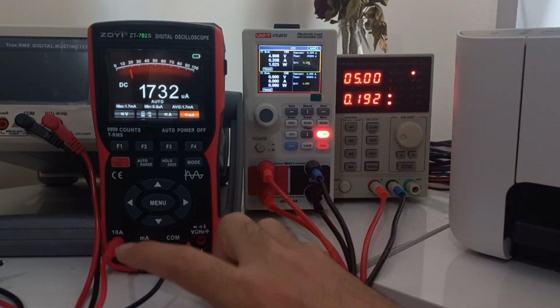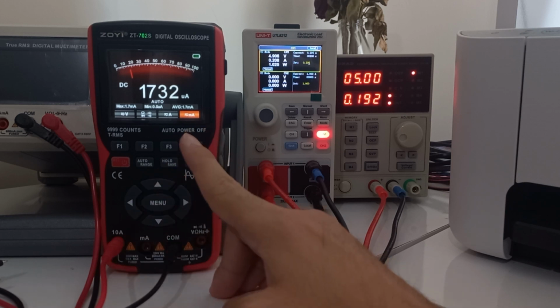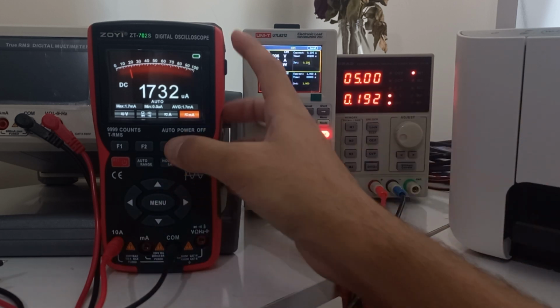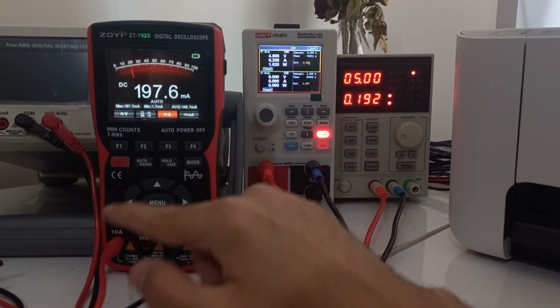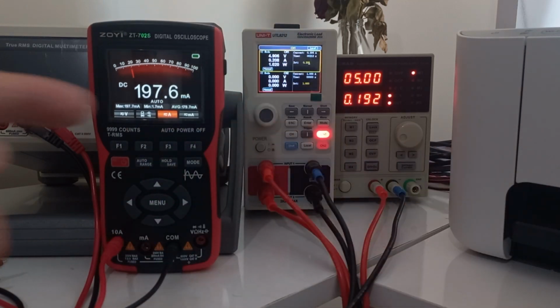Right now we are in the ampere socket but in the milliampere range, which is incorrect. It should go to the ampere range. Once these two match, we are going to get a correct measurement.